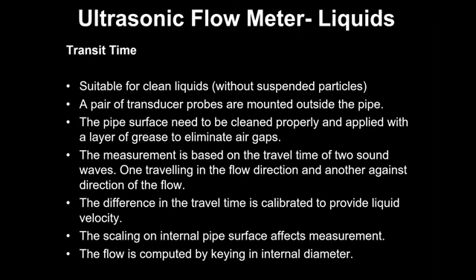The good thing about this instrument is it will give indications. If the readings are not coming, it will give an indication. It will show what signal strength you are receiving. It will also tell you what the distance between the two probes should be, and accordingly you have to set the probes. So that part is made easier by the instrument. It is programmed, so you key in the pipe diameter, pipe thickness, and type of liquid. Based on that, it will tell you the distance between the two probes. You set the probes accordingly and wait for the signal. There will be a signal which tells you that you can rely on the reading.